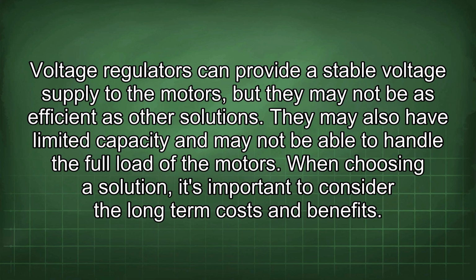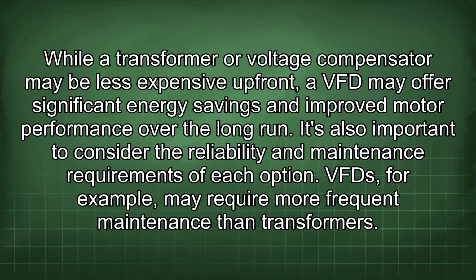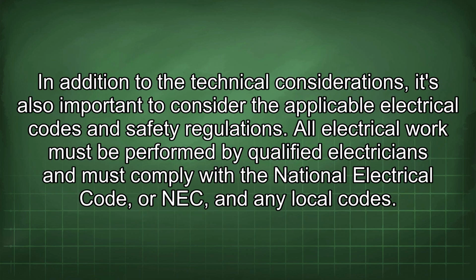When choosing a solution, it's important to consider the long-term costs and benefits. While a transformer or voltage compensator may be less expensive upfront, a VFD may offer significant energy savings and improved motor performance over the long run. It's also important to consider the reliability and maintenance requirements of each option. VFDs, for example, may require more frequent maintenance than transformers. In addition to the technical considerations, it's also important to consider the applicable electrical codes and safety regulations.